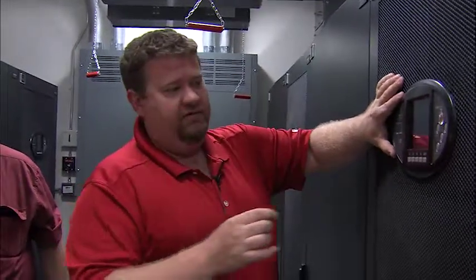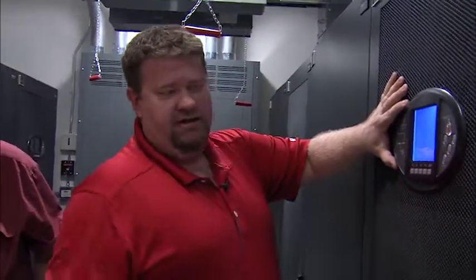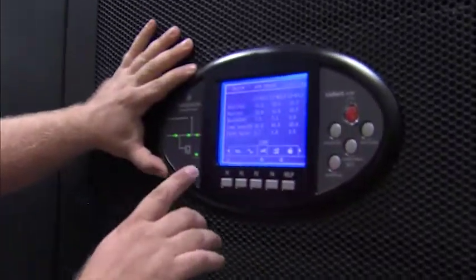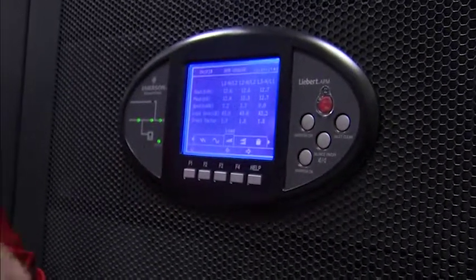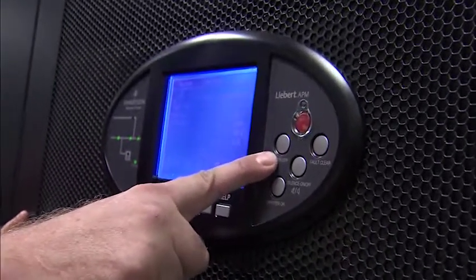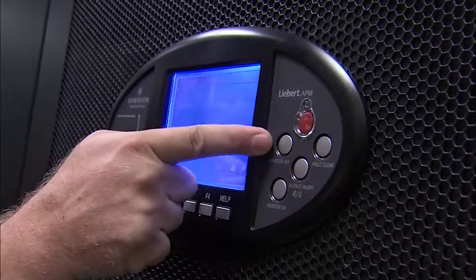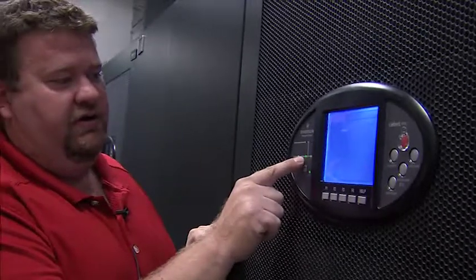And the way we do that, and I'm not going to demonstrate it other than showing. Right now our inverter and rectifier are on. They're being used. So if I came in here and pushed the inverter off button, right here, at that point it will sense the bypass voltage, make sure it's in sync, and then it will send this unit into bypass. So your power path then will be here. Your input and your inverter are gone. Now your power path comes through this way, bypassing all of that.